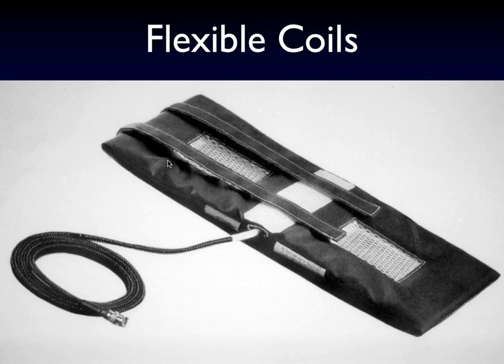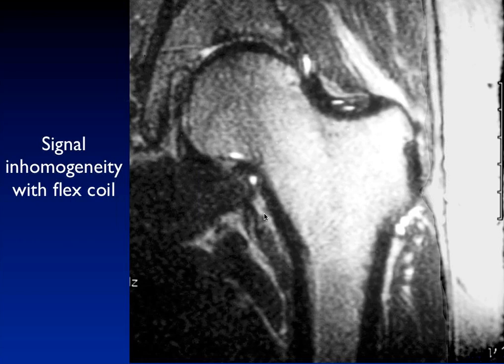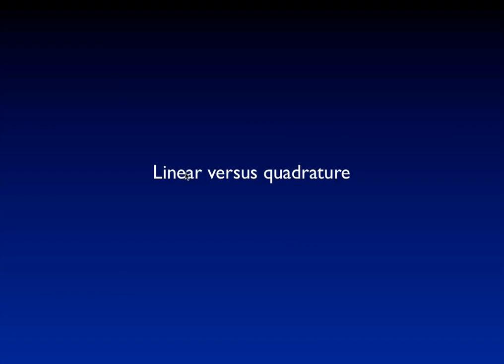Flex coils can also be used. In practice, flex coils are never quite as good as rigid coils for signal intensity, but they are useful at various sites, especially for unusual body parts. Here is a flex coil wrapped around the hip, giving a little more uniform signal intensity, though it still tends to be bright next to the coil with significant drop-off further away.